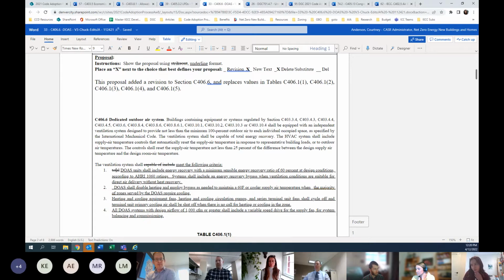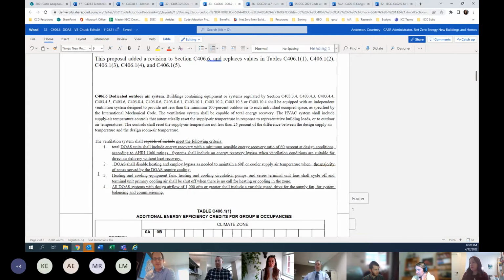One is including energy recovery with a minimum energy recovery, and this is sensible in the Denver climate, of at least 60% at design conditions, according to the ASHRAE ratings. The system shall include an energy recovery bypass when ventilation conditions are suitable for direct air delivery without heat recovery. So we want to make sure, if it's 60, 70 degrees outside, that the energy recovery system, which has a pressure drop and subsequent increase in fan energy, can be bypassed.